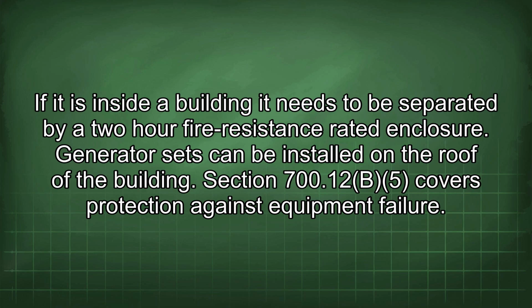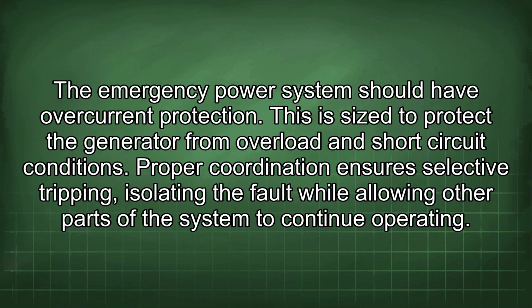Section 700.12(B)(5) covers protection against equipment failure. The emergency power system should have overcurrent protection. This is sized to protect the generator from overload and short-circuit conditions. Proper coordination ensures selective tripping, isolating the fault while allowing other parts of the system to continue operating.